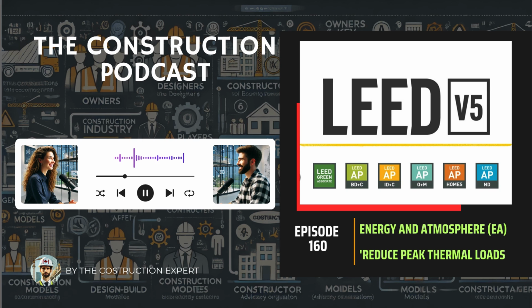Finally, a truly holistic approach means leveraging thermal mass and active energy storage strategies to balance thermal demands effectively. In many real-world applications, the optimal solution isn't just one option, but a smart combination, intelligently drawing from option 2, passive thermal mass, the inherent capability of materials, and option 3, active thermal storage, the mechanical ability to store energy. Using both passive and active approaches together creates a far more balanced, flexible, and resilient building system, one that can handle diverse external conditions more gracefully, respond intelligently to dynamic energy prices or grid signals, and better withstand unexpected stresses like power outages. It's about building a versatile, adaptive energy performer.